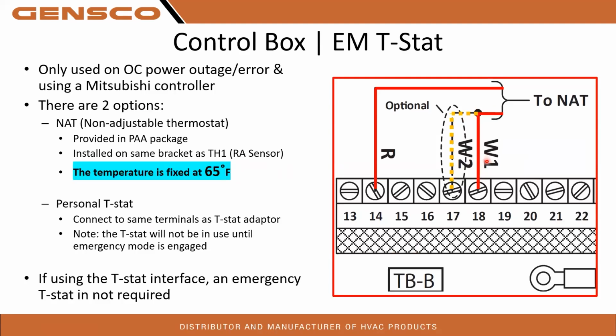All right. This is that non-adjustable thermostat wiring I was talking about. So in the event that there's a power outage to the heat pumps, the heat pump goes into an error, it can't communicate anymore, but the gas furnace is still operational, the system will automatically switch over to the gas furnace to provide backup heat. If you're not using a 24-volt thermostat, so if you're using a Mitsubishi communicating thermostat, that is powered by the heat pump. So if your heat pump goes out or has any kind of errors, the thermostat can no longer communicate. It is going to automatically switch over to this non-adjustable stat. The one that comes in the kit, again, is set for 65 degrees.